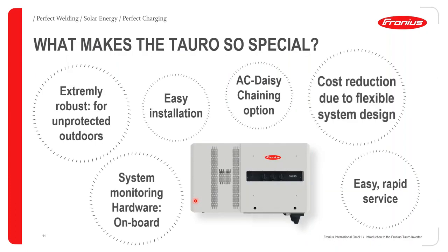What makes the Tauro so special? The first thing is system monitoring. All the hardware is already integrated on board, and this is in the form of the pilot card, which has very similar capabilities to the data manager. The only real advantages of the pilot over the data manager is that with the pilot, we now have possibilities for 2 Modbus RTU ports, and we also have 2 Ethernet ports as well.